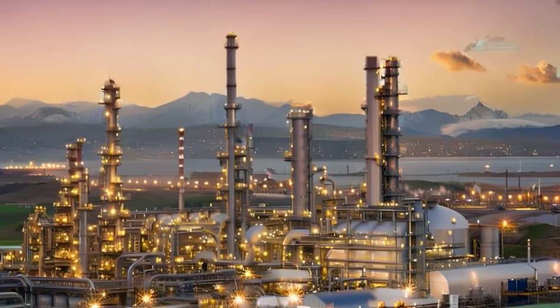For large generators or motors, a vibration isolation system may also be installed to further reduce any transmission of vibrations to the surrounding structure and to protect the machine itself from external vibrations. 3.2 Alignment and coupling. Correct alignment between the rotating shafts of motors and the driven equipment such as pumps, compressors, etc. is vital. Misalignment can lead to excessive vibrations, premature wear of bearings, shaft damage, and reduced efficiency. In the oil and gas industry, where precision in operation is key, laser alignment tools are commonly used to achieve precise alignment, ensuring that the shafts of the motor and the driven equipment are perfectly aligned. This not only extends the lifespan of the machine, but also reduces the risk of failures and downtime.